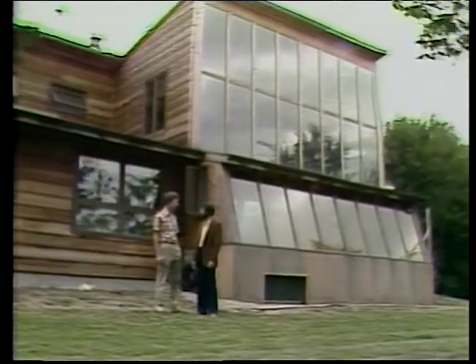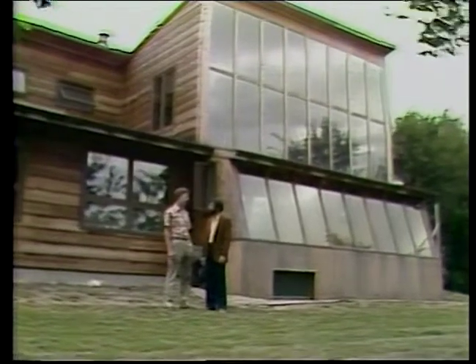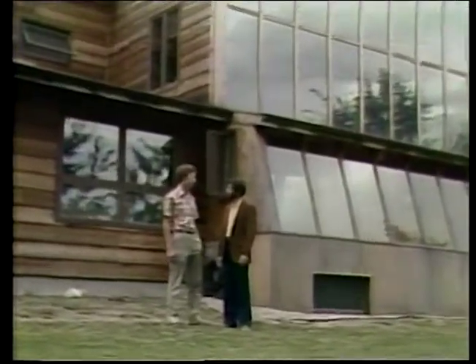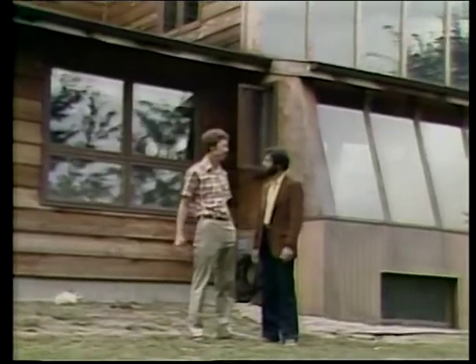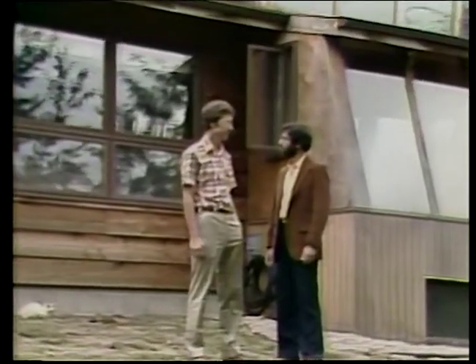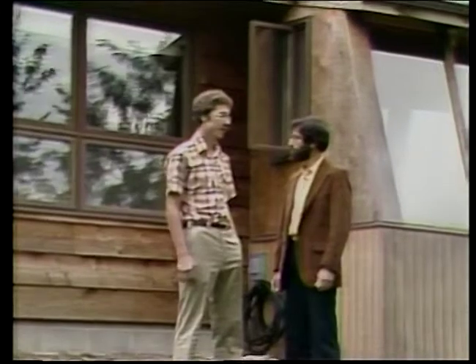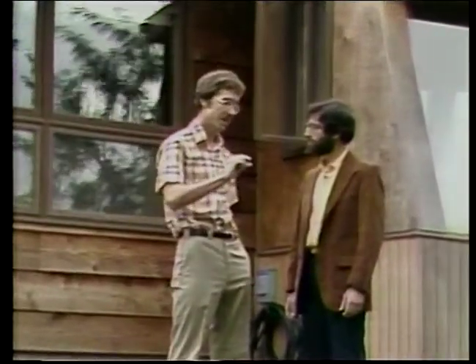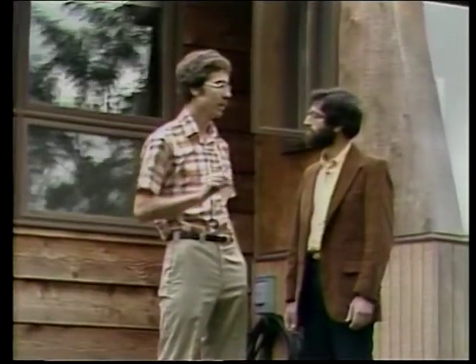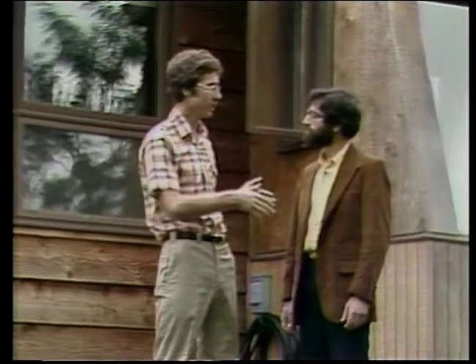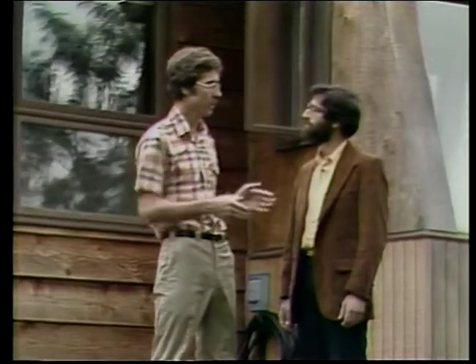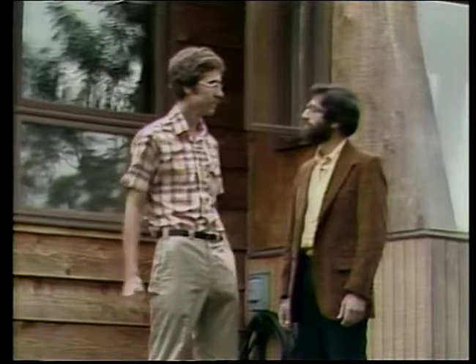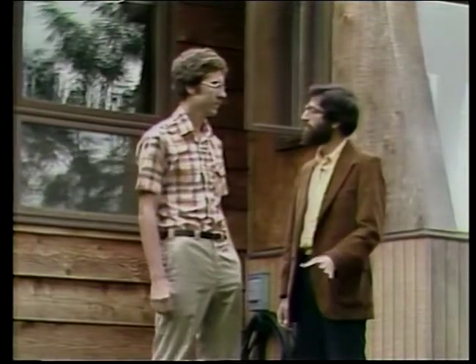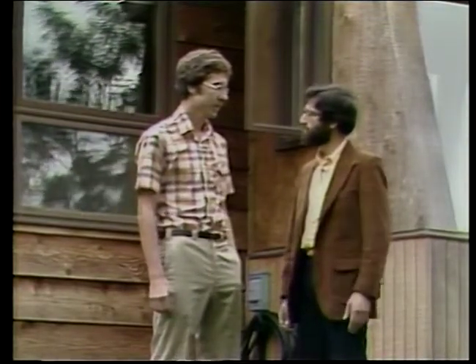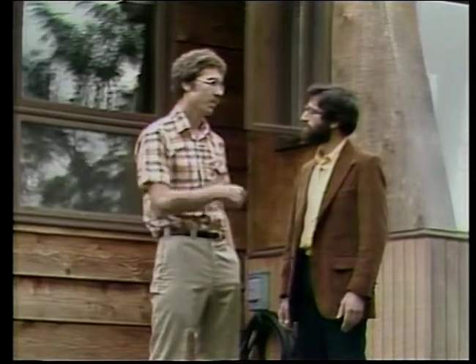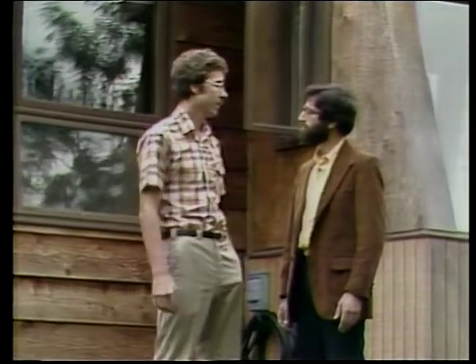And what kind of storage system do you have? We have a phase change material, eutectic salt, which melts at 90 degrees Fahrenheit. And the air blows over the salt? Yeah, the salt is contained in thin plastic trays, and we have 1,400 of these trays stacked up in an insulated storage room, and then the air blows through the trays. I see. Now, how long can you store heat in the salt? What we found here, it will last about one day. I see.